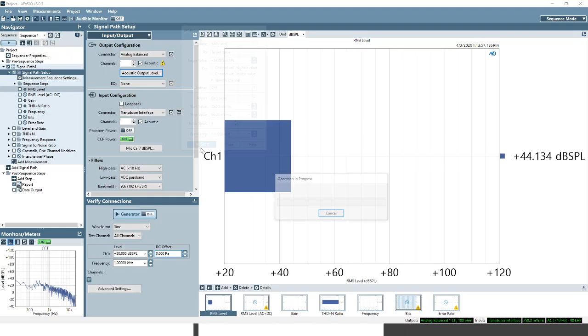I realize in this case, actually, I may not be going low enough. Let's lower this down a little bit. It's possible that 84 dB SPL is a little under where my initial test was; actually, my initial test was at 94 dB SPL before I realized it was kind of cranking in my house. There we go. Okay, so now I've regulated to 84 dB SPL, and I can see on my generator down here that as I have 84 dB SPL set as my output level, that is indeed what I'm measuring more or less at my input.